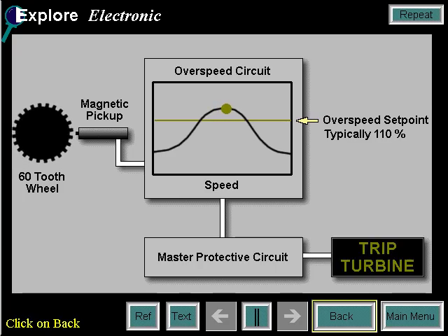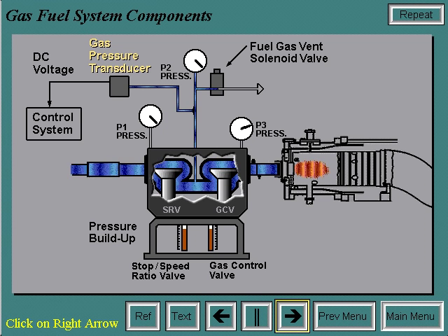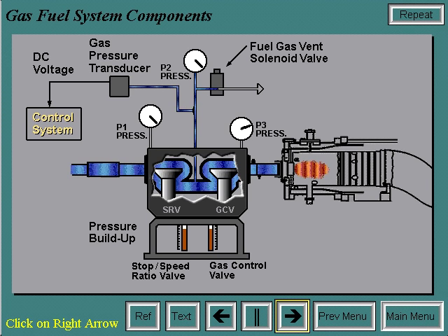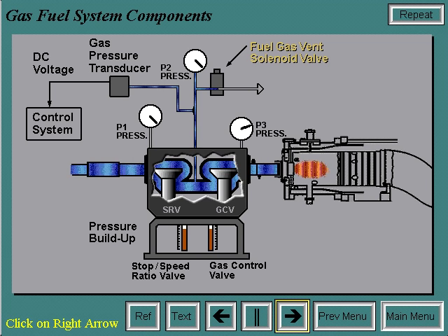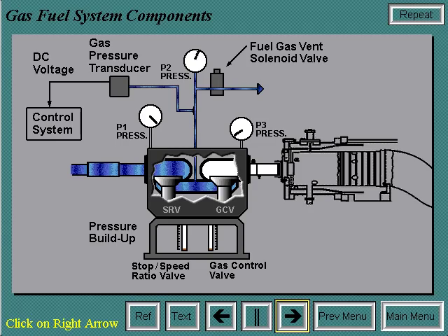An electrical overspeed trip message will be displayed. The fuel gas pressure transducer has a DC voltage output directly proportional to pressure input in PSIG. This transducer provides the control system with a feedback signal for the operational fuel gas pressure, or P2 pressure, between the stop speed ratio and gas control valves. The fuel gas vent solenoid valve vents the volume between the stop speed ratio valve and the gas control valve when the solenoid is de-energized. This valve is closed during operation; when open, it ensures that during shutdown, fuel gas pressure will not build up and no fuel gas will leak past the closed gas control valve.